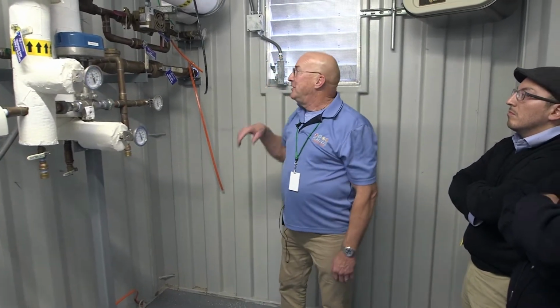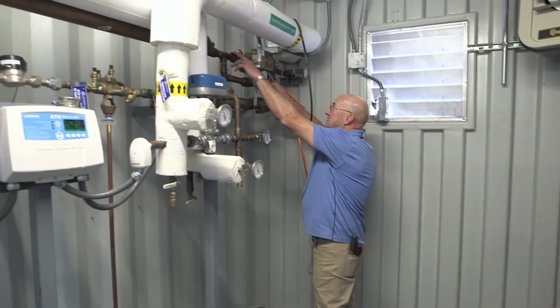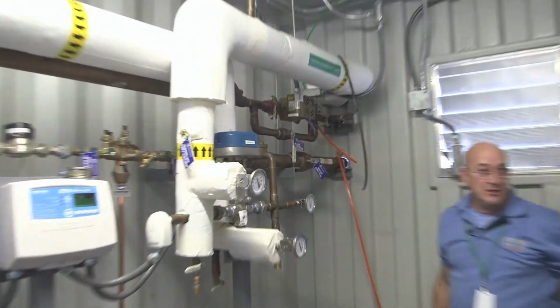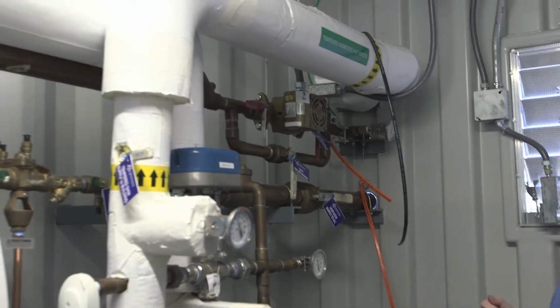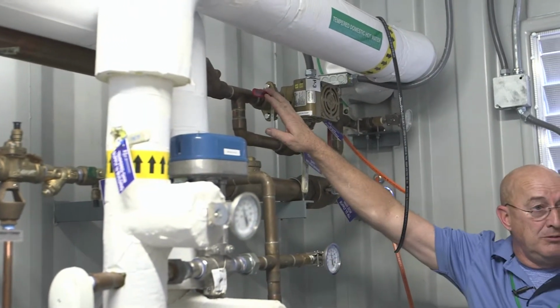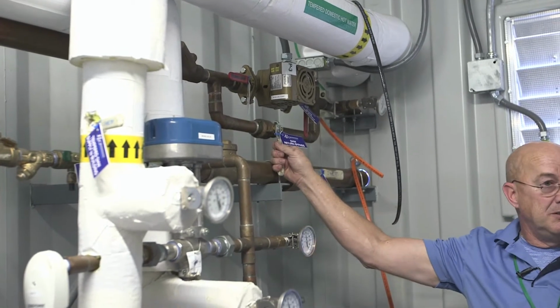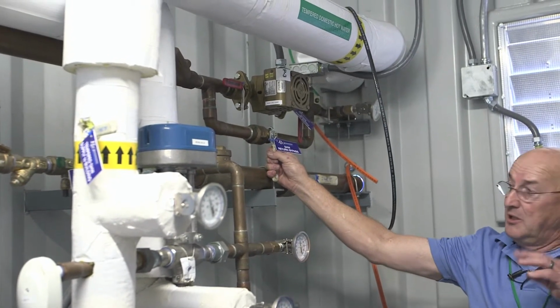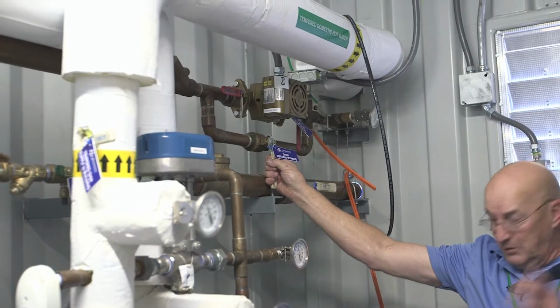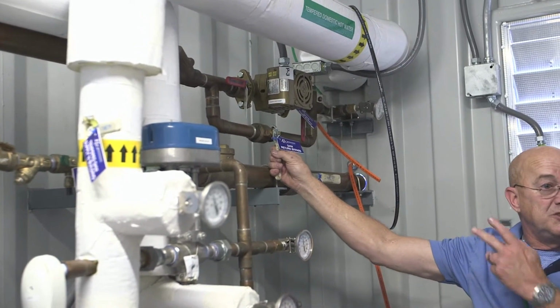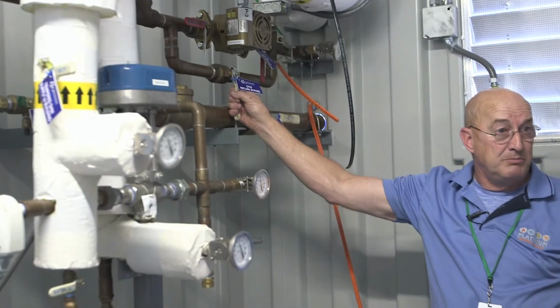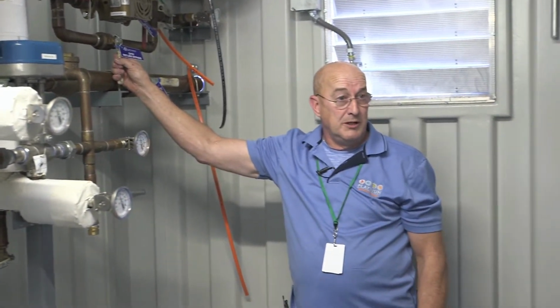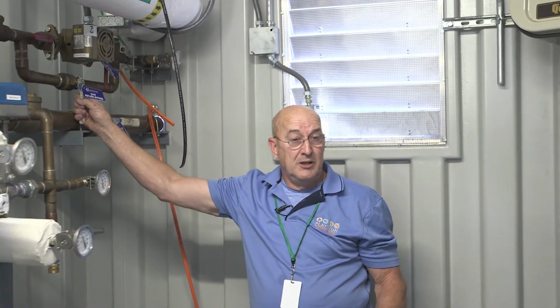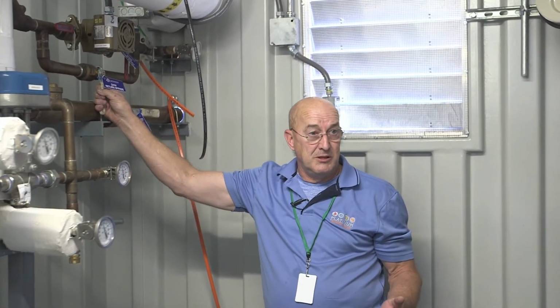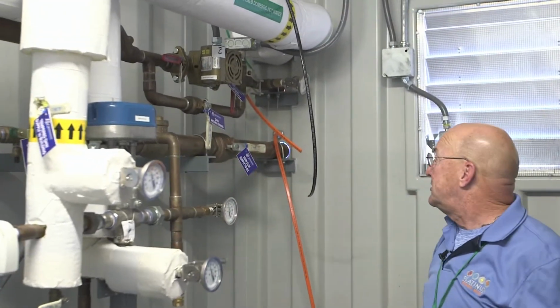All right. Everything has isolation valves. There's isolation valves on each side. If you get a water leak in the pump, just shut both of these down. You have a bypass here. You open up the bypass, it won't be a circulator run line, but it'll be gravity. So at least temporarily, until somebody gets here to replace the pump, you'll have hot water. Not as perfect. It may take 2 or 3 minutes if they open the faucet, but it's not going to take 20 minutes. All right, so that takes care of that here.